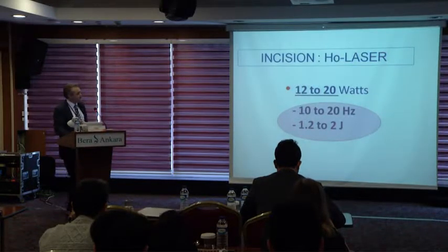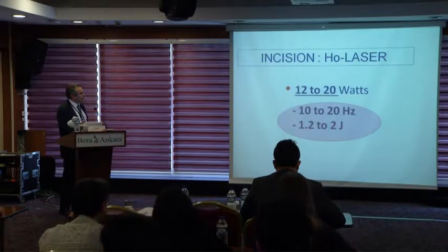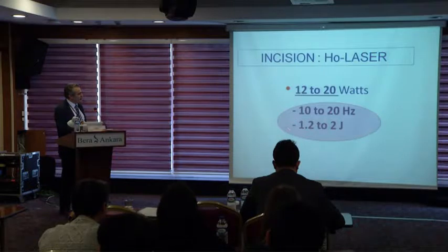What about incision? During the incision, you have to increase your power and you have to increase your frequency above 10, near 20 hertz, and you have to increase also your power.